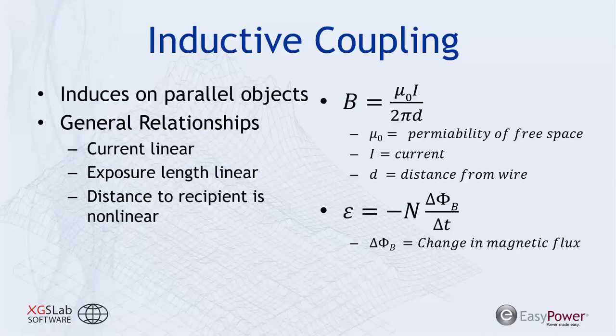And if you're changing the distance from your transmission line to the recipient object, that's going to result in a nonlinear relationship. And you can kind of see that from the equations on the right. We have the magnetic field strength, which is the permeability of free space times the current over the distance from the wire, and how much that changes in a relative period of time is going to determine your induced voltage on that adjacent object. So you can have much greater field strength changes in a little bit shorter distances from that transmission line.